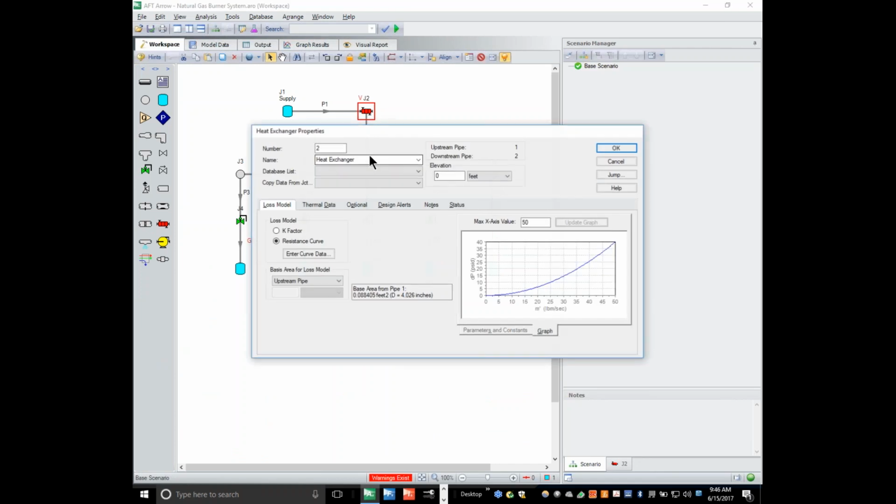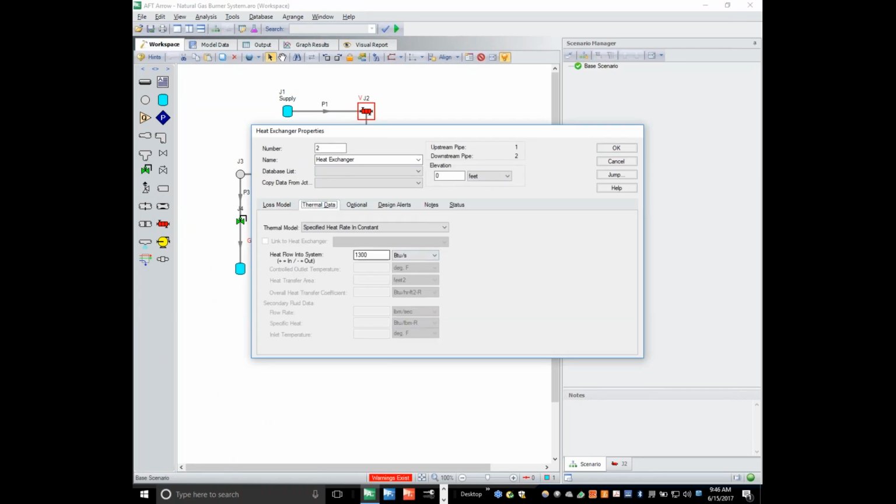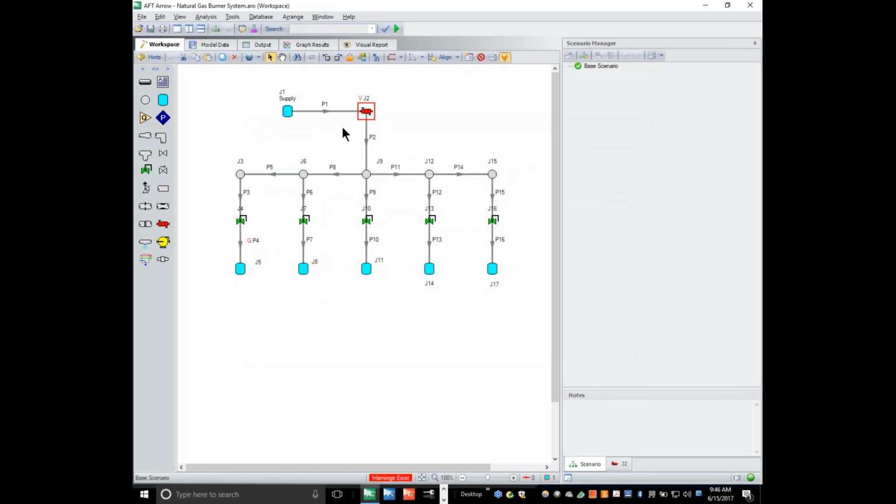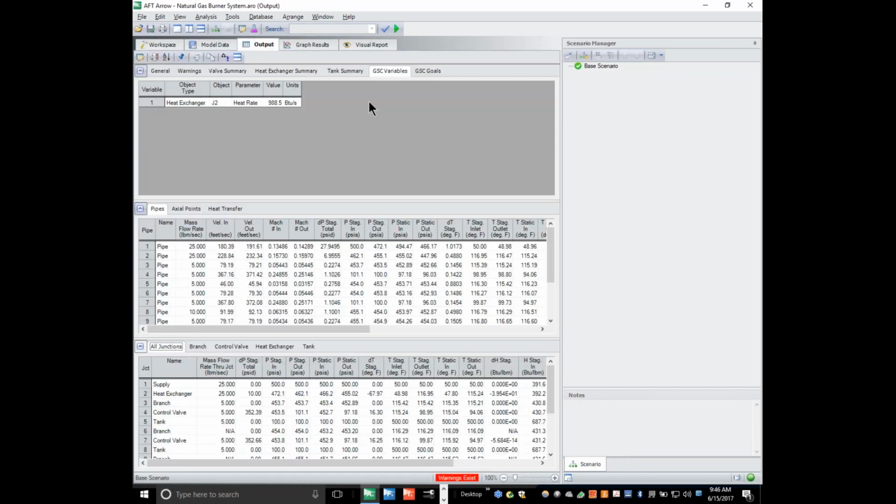Perhaps we gave it a poor starting condition, so if we change this to 1100, that would give us 1,006 BTUs per second, very close. It's close initially, so those results would still be usable. Remember, most people would probably stop around 1,000 BTUs per second when they're determining that. And we can see how far off we actually were.